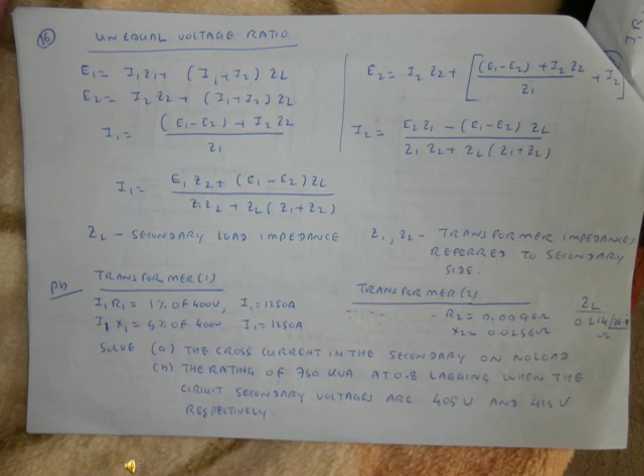So we have to solve the problem. Transformer 1: I1 R1 is 1% of the 400 volt, I1 is 1250 ampere. I1 X1 is 5% of the 400 volt, I1 equal to 1250 ampere. Transformer 2: R2 is 0.0096 ohm, X2 is 0.0256 ohm, ZL is 0.214 angle 36.9 degree ohm. We have to find A, the cross current in the secondary on no load, and B, the current sharing of the 750 kVA load at 0.8 lagging, when the open circuit secondary voltages are 405 volt and 415 volt respectively.